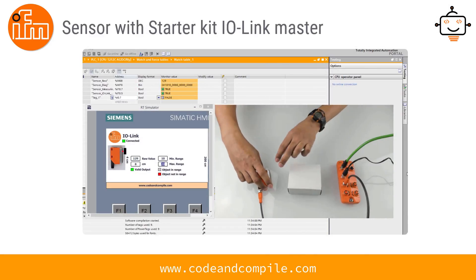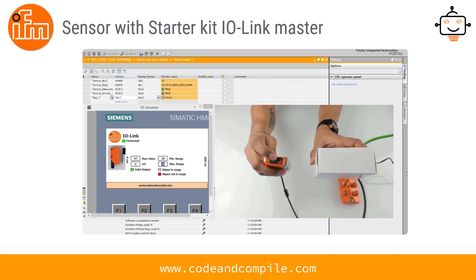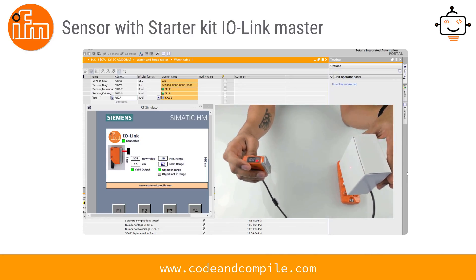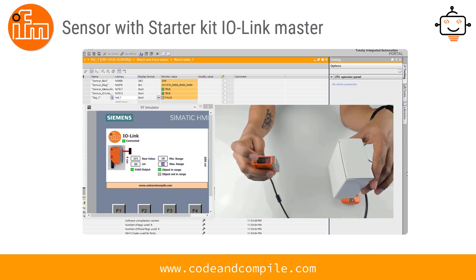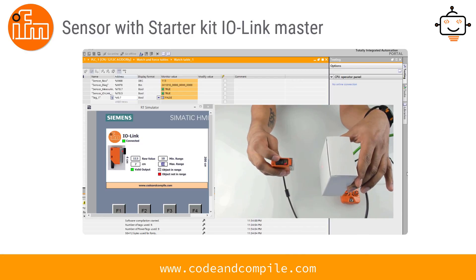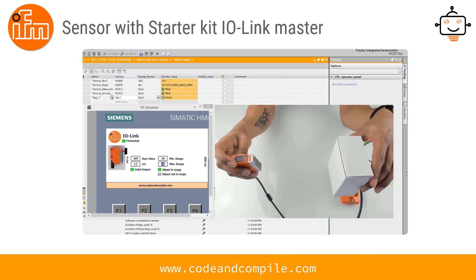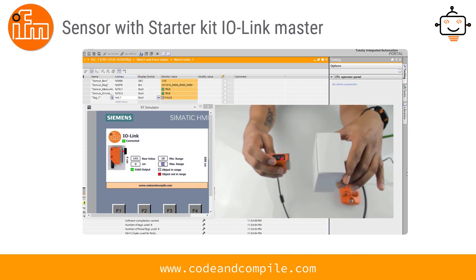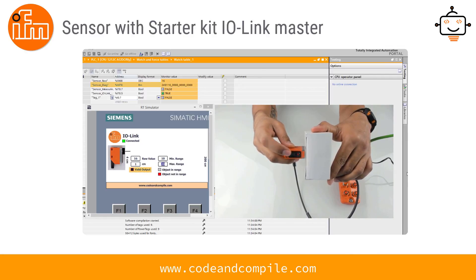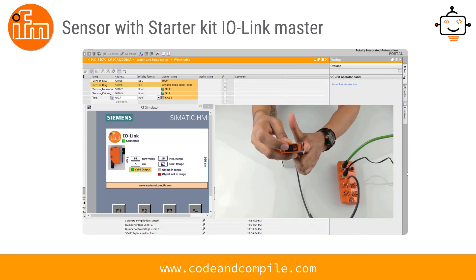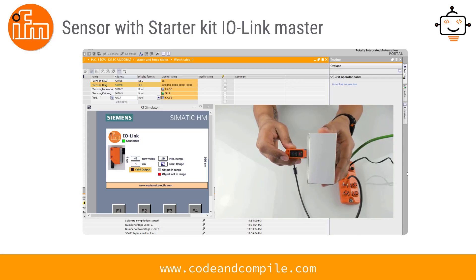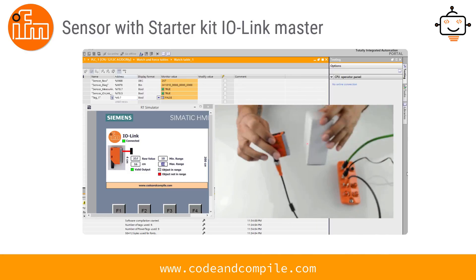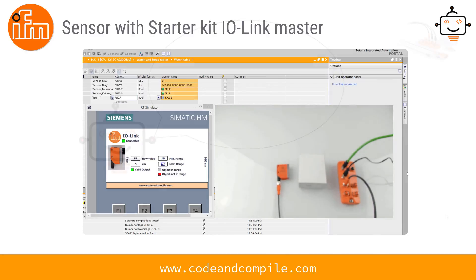Now we'll see the sensor used with the IO-Link master. With the sensor linked to the PLC, you can read the distance information directly in the PLC, and it is reflected on the HMI. With this analog information you can design proportional logic based on how far the object is from the sensor. You can also see diagnostic information on the HMI. When the object is too close, the valid output bit goes false, indicating the sensor is dusty or needs to be cleaned. This differentiates sensor behavior from normal operation, where you get the full distance range.